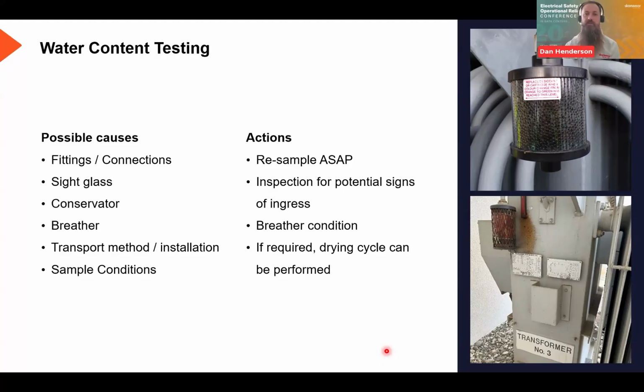So again, there's lots of different causes. As I mentioned, it could be an integrity issue. So any fittings or connections, which might be on the radiators or pipework, the sight glass, the conservator. So in that example there, in the picture, you can see there's a leak in the sight glass. Potentially you could get water ingress there. The breather on free breathing transformers. So this is such a common thing that I see on sites where I go and do a site inspection, and for something that's such an easy maintenance task, it's neglected.